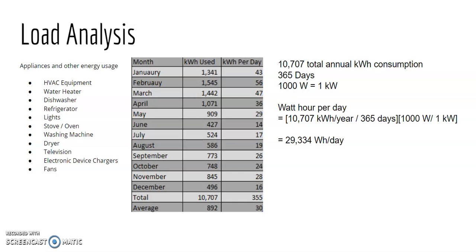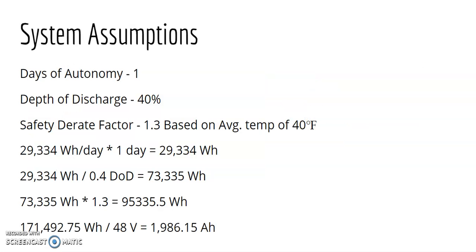And to find the watt hours per day, I took the total kilowatt hours used of 10,707, divided that by the number of days, and converted to watts by a factor of 1,000 watts equals 1 kilowatt. And this gave me an exact number of 29,334 watt hours per day, compared to the averaged 30 kilowatt hours per day of use, which would have been 30,000 watt hours per day. We just wanted to be a little more exact in our analysis.